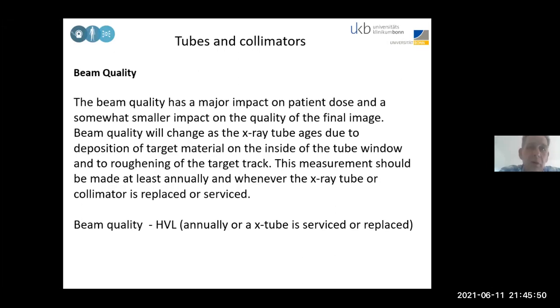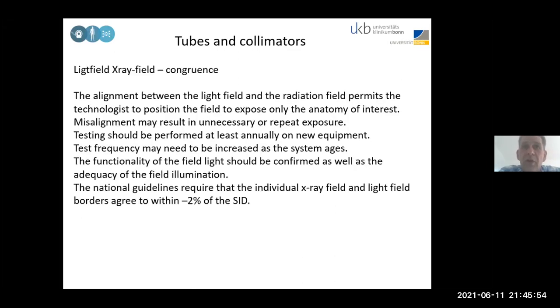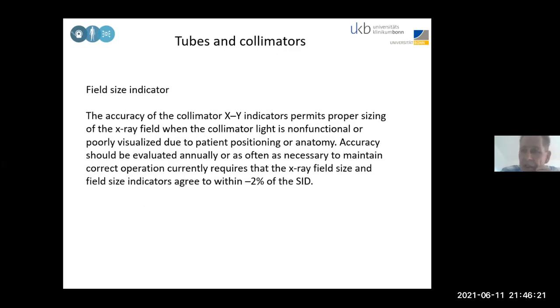I actually recommend semi-annually. Light field and X-ray field congruence is also very important. If you try to put your patient into a certain situation, then you adjust your X-ray device with a light field. But you really have to check whether your light field and your X-ray field coincide. And at least 2% of the SID is the tolerance you should not exceed there. Field size indicator. So on the field size, there's maybe written, now you have 20 by 18. And then you check 20 by 18 and it is 21 by 19. So there, you should say that the indicator of the field size and the real field size should not differ by more than 2%.